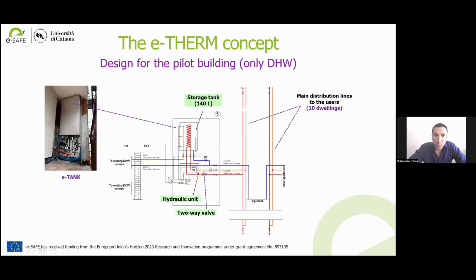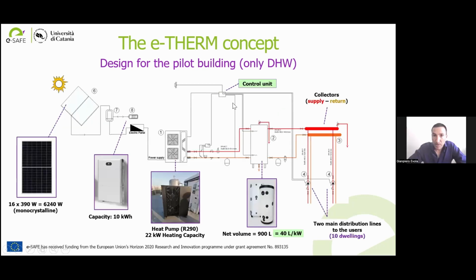In this case, to prevent Legionella, by law in Italy, for instance, this water must be kept at least at 60 degrees Celsius. Instead, in our thermal system, the water coming from this tank is technical water. It is used to charge the tank with thermal energy. And the users draw water from this tank, which means that inside the large centralized tank, we don't need to provide Legionella protection, and we can use lower temperatures. For instance, 55 or even 52 degrees instead of 60 or more. This is important because heat pumps in the e-THERM system can work with lower temperatures and then with higher COP. This is the first difference.